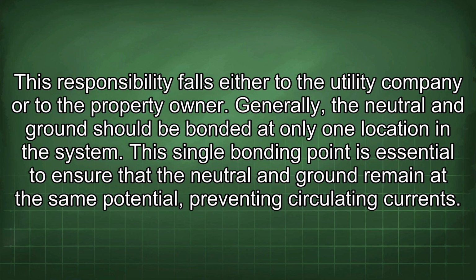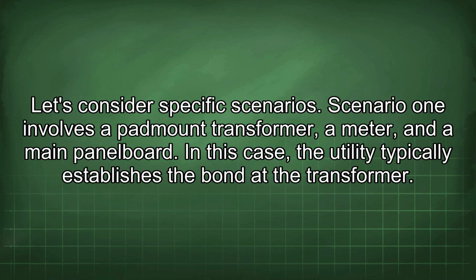Generally, the neutral and ground should be bonded at only one location in the system. This single bonding point is essential to ensure that the neutral and ground remain at the same potential, preventing circulating currents. Let's consider specific scenarios.